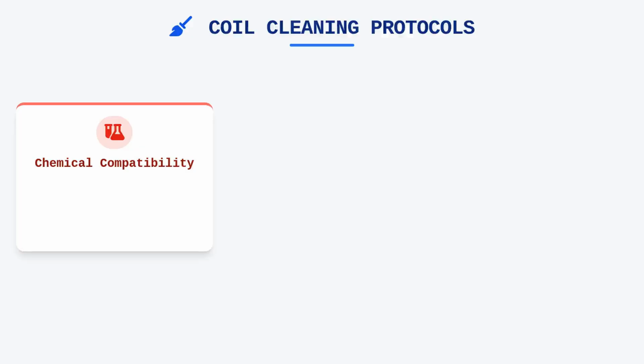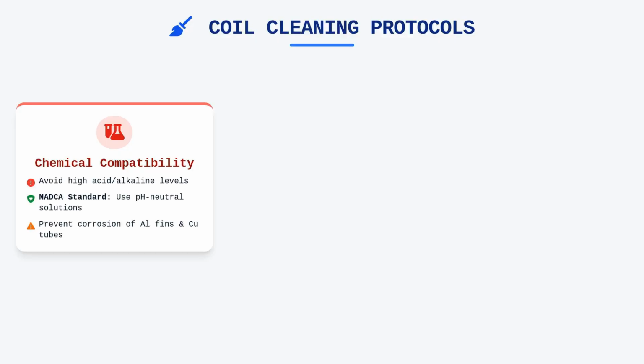When we arrive at a unit to clean these components, we must prioritize chemical compatibility to avoid permanent damage. Many coil cleaners are highly acidic or alkaline, which can corrode aluminum fins or copper tubing if not thoroughly rinsed or if the chemical balance is wrong. NADCA standards strongly advise the use of pH-neutral cleaning solutions whenever possible to minimize the risk of degrading the protective oxide layer on the metal.